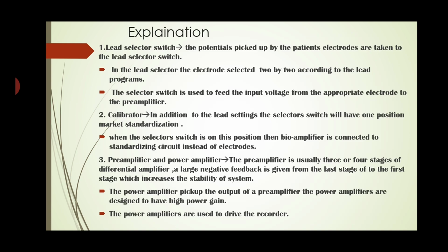Third, preamplifier and bioamplifier. The power amplifier is nothing but the bioamplifier. The preamplifier is usually three or four stages of differential amplifiers. A large negative feedback is given from the last stage to the first stage of the amplifier, which increases the stability of the system. The power amplifier picks up the output of the preamplifier. The power amplifier is designed to have high power gain and is used to drive the recorders. So obviously the power of the signals will be increased in the power amplifier.